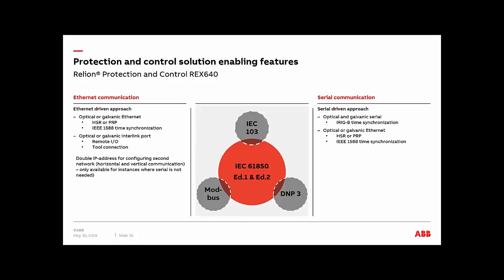When it comes to communications, the relay is equipped, if ordered with a specific option, with high-speed HSR ring or parallel redundancy with PRP. And we also have IEEE 1588 time synchronization, which is going to be needed if you're implementing some type of sample values or IEC 61850 process bus. So the optical galvanic interlink port, where you can have a remote input-output, or you can connect to the different engineering tools.